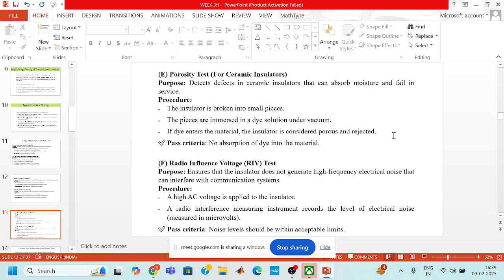Now, fifth is the porosity test. The porosity test is done for ceramic insulators. It detects defects in ceramic insulators that can absorb moisture and fail in service. First of all, the insulator is broken into small pieces. Then the pieces are immersed in a dye solution under vacuum. If dye enters the material, the insulator is considered porous and rejected. If there is no absorption of dye into the material, the insulator will pass the porosity test.